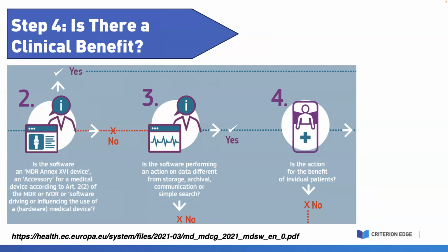So in addition to the clinical evaluation or the performance evaluation of your device, remember, we're going to be needing to consider the benefit-risk ratio in light of the state of the art. And that's going to help us with really drilling down on this point of the clinical benefit. There are a lot of different aspects that are specific hazards that could need to be introduced into this assessment of that benefit-risk. Those can be everything from the type of disease, the patient's condition, the usability, all the way down to how the software is designed and some of the technical characteristics of the platform for that software. So there's a lot of considerations that you're going to want to take into account when determining that benefit-risk analysis for software in particular.